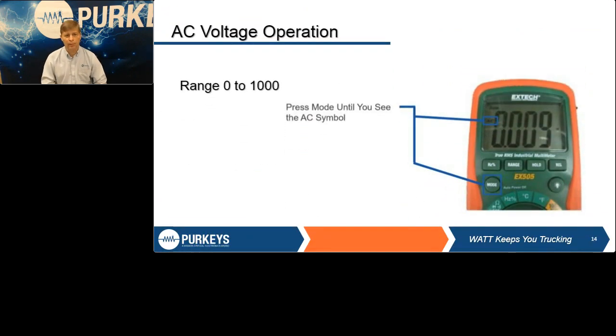And the other thing, too, is you got to make sure what your meter is capable of reading. These particular meters we're showing here will read up to 1,000 volts, whether AC or DC. If you should try to read something over 1,000 volts, again, it's going to read that OL. You're out of limits, out of luck, whatever you want to call it, that you're above the capacity of that. So it doesn't mean there's nothing there if you get an OL. You're just beyond the capacity of that meter. And I've said it before, and I'll say it again, that you get what you pay for.